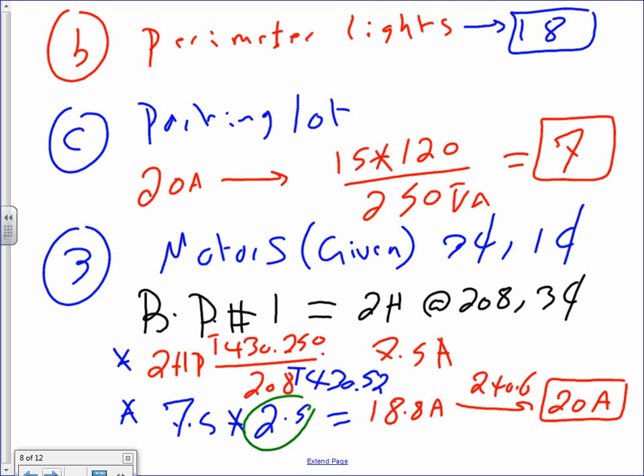Parking lot. Here's the parking lot. 20 amp circuit, always. 15 times 120 divided by... where did I come up with 250 volt amp? Typically, metal halide in a parking lot, unless you know otherwise, 250 is what we use for this type of commercial. So if you divide by 250, how many of them can you get? 7 of them. 7 fixtures outdoors on 1 circuit. If you have 8, split them into 2 circuits. Can I have a thumbs up, Chad?